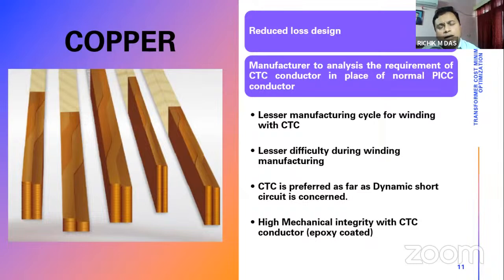Here I want to say that manufacturers have to analyze whether they go for CTC conductor or normal PICC conductor, because CTC conductor has a great advantage in this aspect. There is a lesser manufacturing cycle for winding with CTC, and lesser difficulty during winding manufacturing. CTC is preferred as far as high dynamic short circuit is concerned, with high mechanical integrity with epoxy coated CTC conductor.